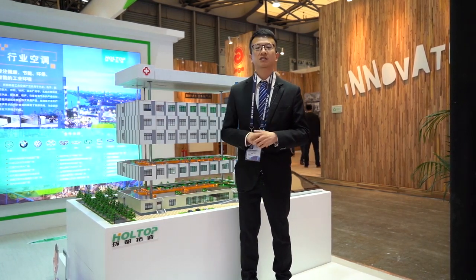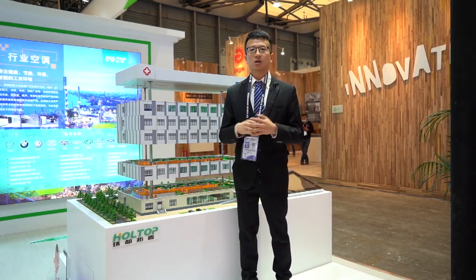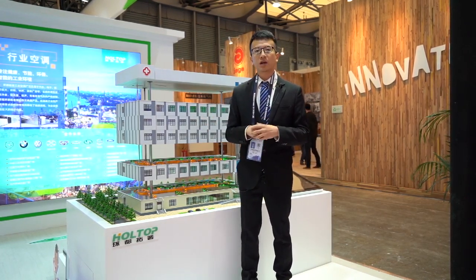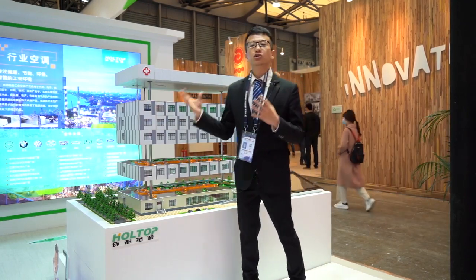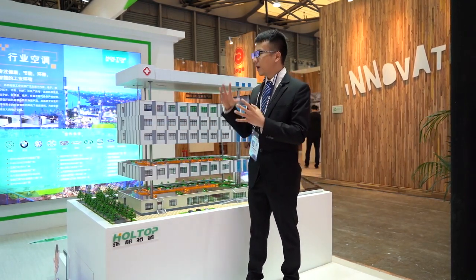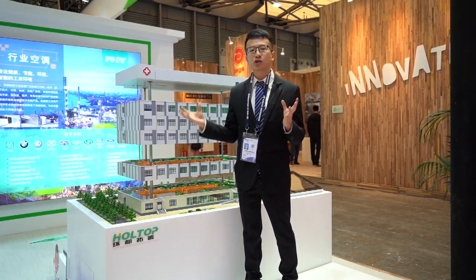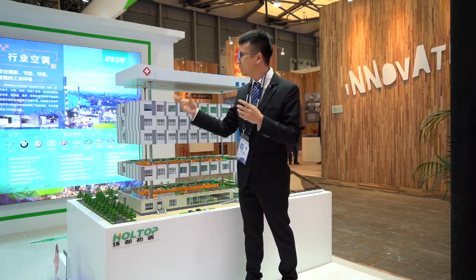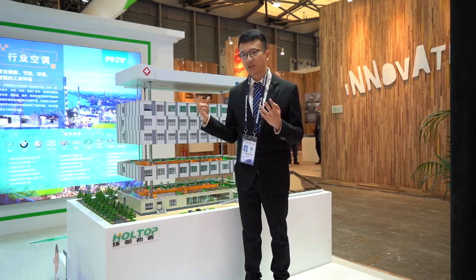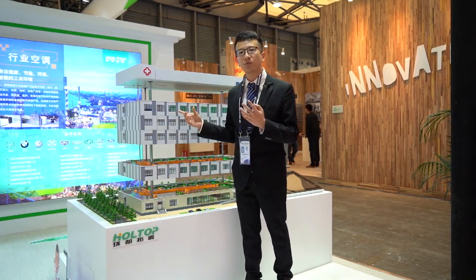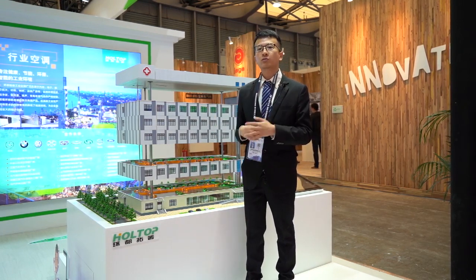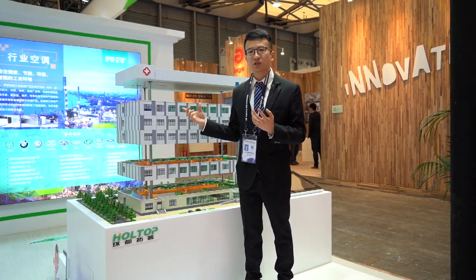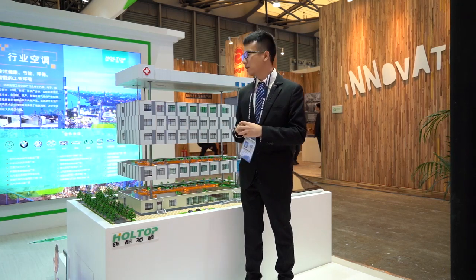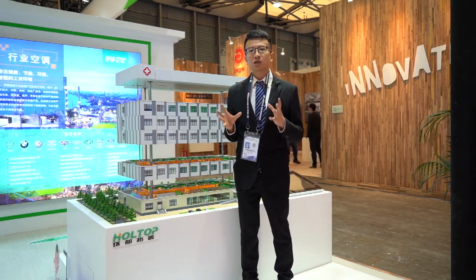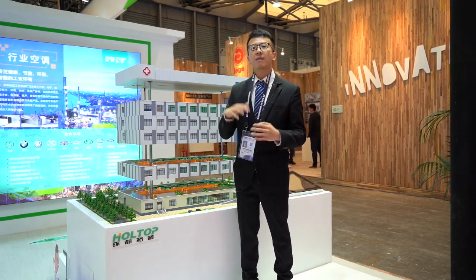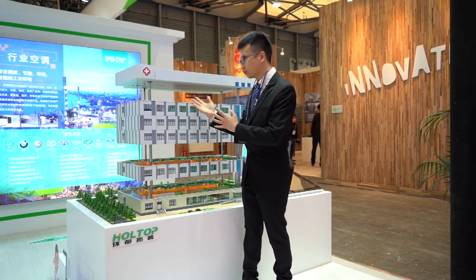This is the major principle to design the fresh air flow route in this smart system. The second one is to identify the minimum fresh air for each room. As we introduced earlier, we can preset the minimum fresh air for each room. For example, maybe in this room there are normally only 2 people inside, and in the next room maybe there are 5 or 10 people, which means this room should have larger and more fresh air. So it is important to design the minimum and maximum fresh air for each room.